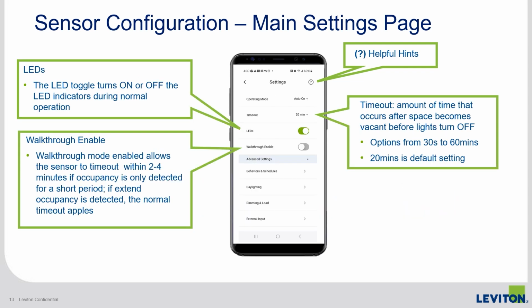Continuing with programming options on the main settings page. Timeout is the amount of time that occurs when the lights will turn off after a space becomes vacant. 20 minutes is the default, but there are options from 30 seconds to up to 60 minutes. The LED toggle allows you to disable or turn off all LED indicators during normal operation. This is for applications where the LEDs could be distracting, such as hospitals or classroom applications.